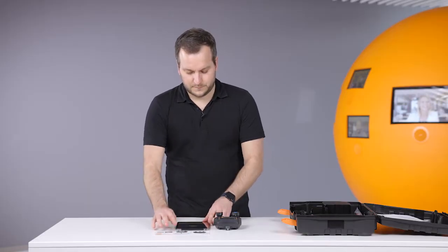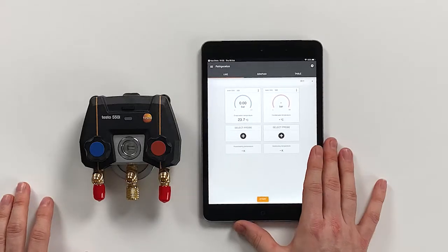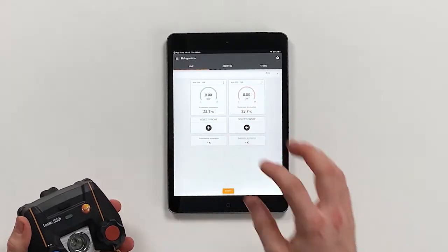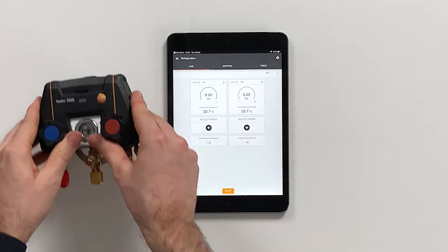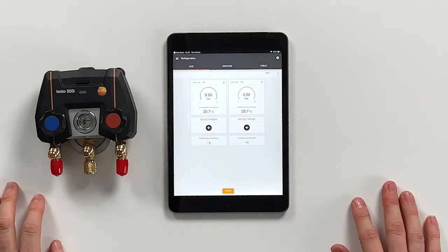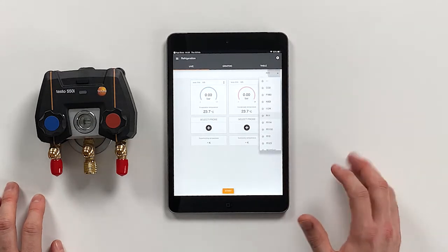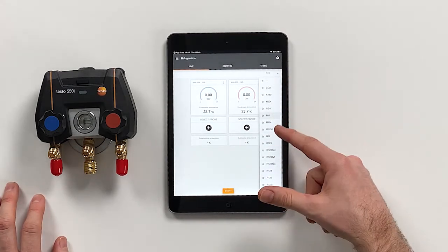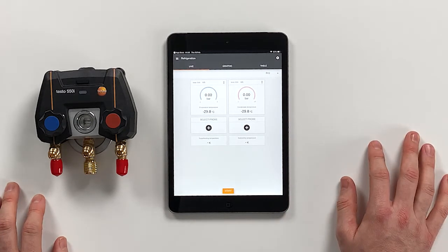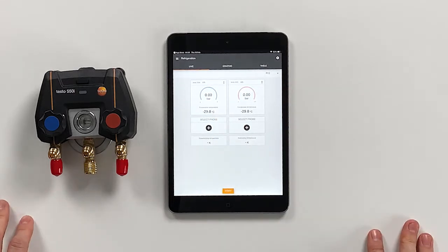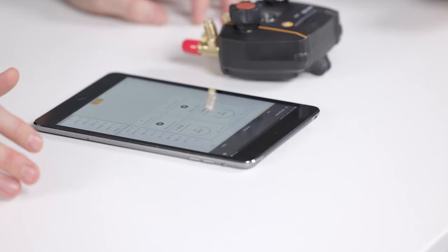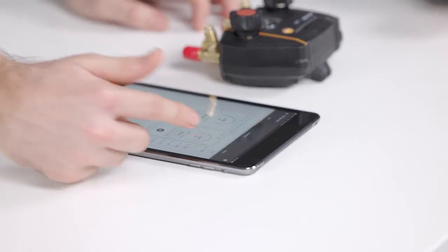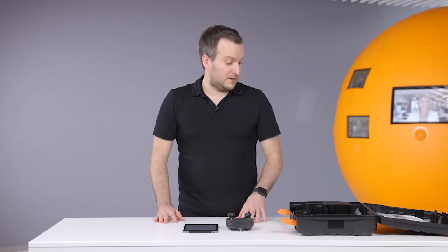On the app, the instrument directly connected. You can also see the green LED. Now we have connected, we can see the 550i with the low pressure side and the high pressure side. As refrigerant we have chosen R410A, but we can choose any refrigerant we want. Let's say R32, and the theoretical temperatures will adapt accordingly. There's also the possibility to set refrigerant favorites, so this will now move up the list.